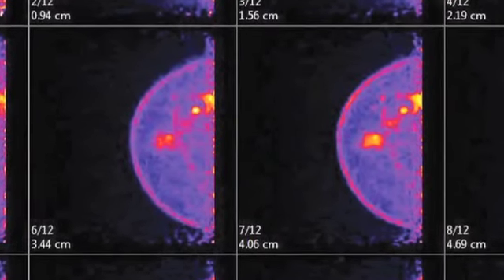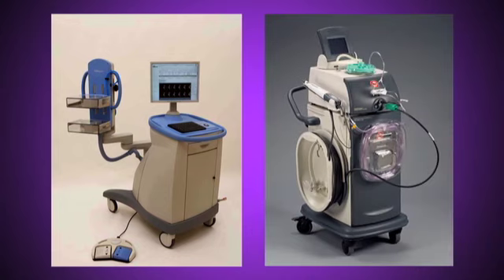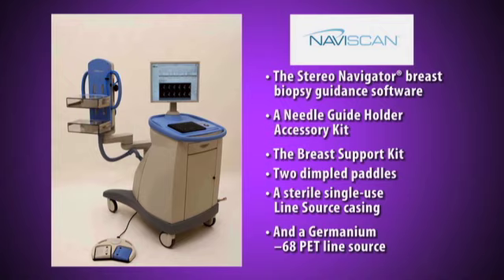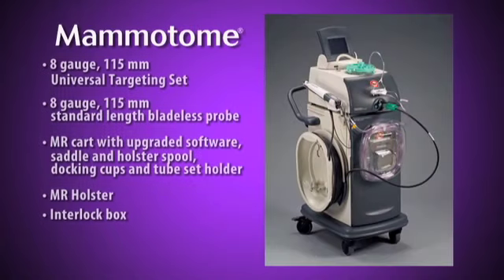To perform an image-guided breast biopsy with PEM, two sets of components are used: the PEM imaging components and the Mammotome breast biopsy components. The PEM components consist of the Stereo Navigator breast biopsy guidance software, a needle guide holder accessory kit, the breast support kit, 2 dimpled compression paddles, a sterile single-use line source casing, and a germanium 68 PET line source. The Mammotome components used for molecular imaging biopsy guidance include an 8-gauge 115mm universal targeting set, an 8-gauge 115mm standard-length bladeless probe, an MR cart with upgraded software, a saddle and holster spool, docking cups, a tube set holder, an MR holster, and an interlock box.